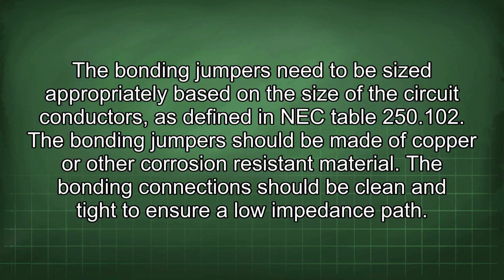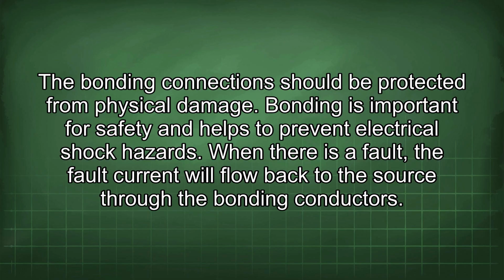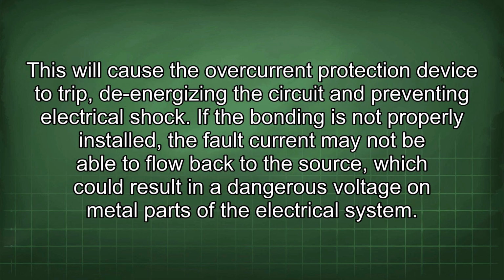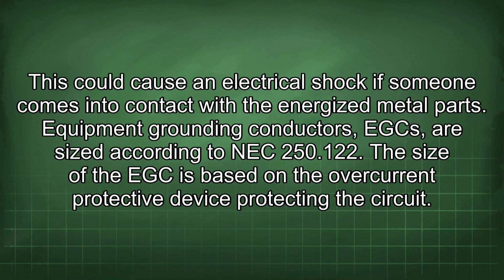The bonding connections should be clean and tight to ensure a low impedance path. The bonding connections should be protected from physical damage. Bonding is important for safety and helps to prevent electrical shock hazards. When there is a fault, the fault current will flow back to the source through the bonding conductors. This will cause the overcurrent protection device to trip, de-energizing the circuit and preventing electrical shock. If the bonding is not properly installed, the fault current may not be able to flow back to the source, which could result in a dangerous voltage on metal parts of the electrical system. This could cause an electrical shock if someone comes into contact with the energized metal parts.